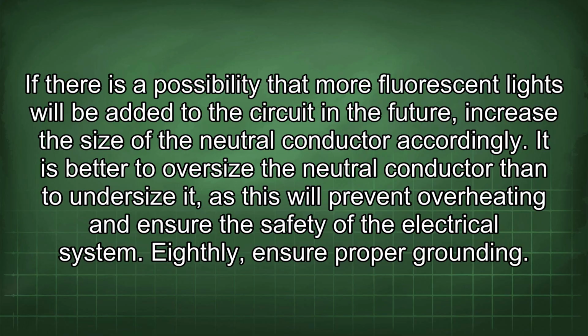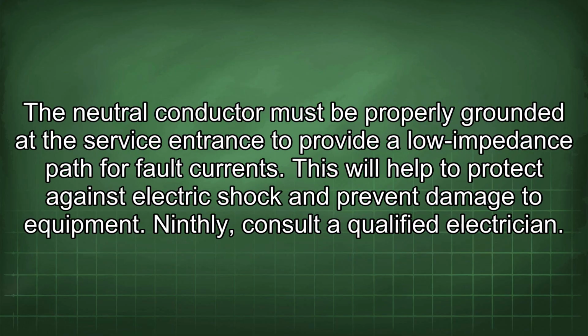It is better to oversize the neutral conductor than to undersize it, as this will prevent overheating and ensure the safety of the electrical system. Eighthly, ensure proper grounding. The neutral conductor must be properly grounded at the service entrance to provide a low impedance path for fault current. This will help to protect against electric shock and prevent damage to equipment.